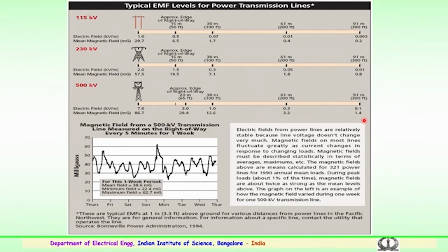The electric fields from the power lines are relatively stable because the voltage does not change. All the transmission lines operating at a particular voltage, say at the 765 kV level, will have very little voltage fluctuation. Because the voltage level is maintained, the electric fields will be relatively stable, but the magnetic fields on the lines may fluctuate greatly, because of current changes in response to the changing load. As the load supplied by the transmission changes, the current magnitudes change drastically.